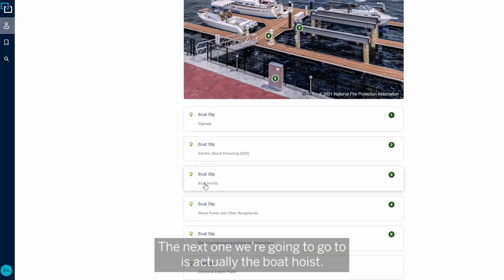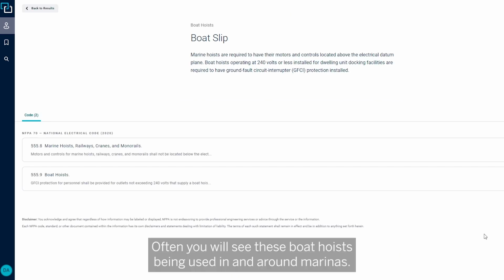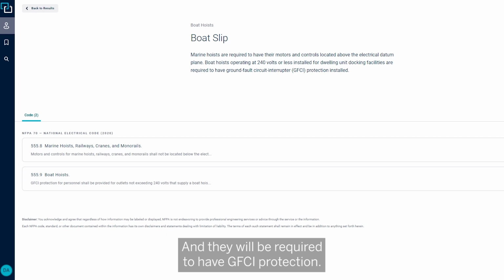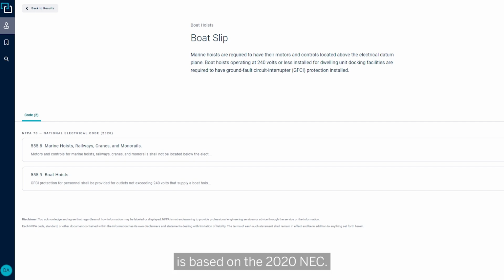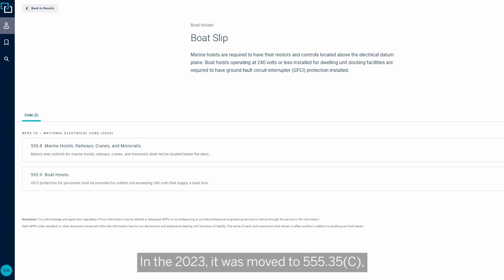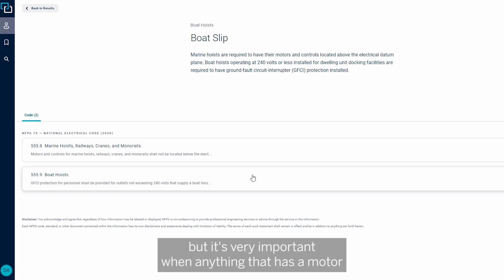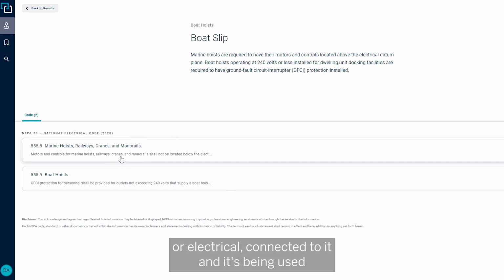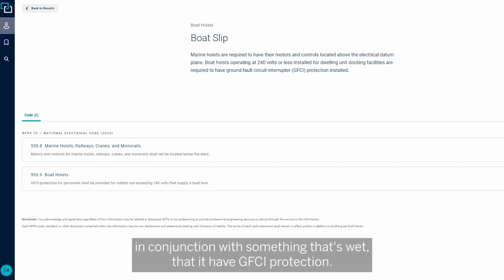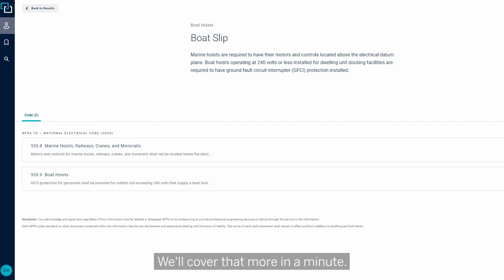The next one we're going to go to is actually the boat hoists. Often you will see these boat hoists being used in and around marinas, and they will be required to have GFCI protection. Just an FYI, this review that we're going over today is based on the 2020 NEC. In the 2020 NEC, GFCI protection is covered in 555.9. In the 2023, it was moved to 555.35C. But it's very important that anything that has a motor or electrical connected to it and is being used in conjunction with something that's wet has GFCI protection. We'll cover that more in a minute.